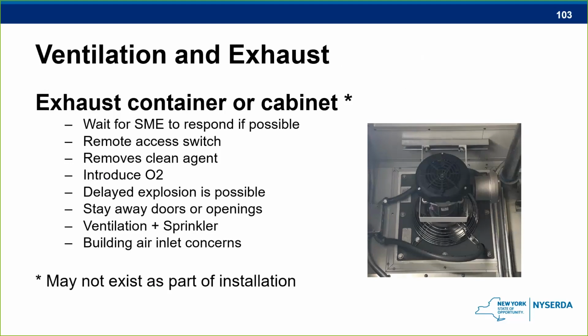But as I also mentioned, during an abnormal situation in lithium-ion, if we get that flammable cocktail and now it's stuck inside the enclosure itself, how are you getting that stuff out of there? And this is what some people are adding into their enclosures. If that stuff comes out automatically, where it doesn't get trapped inside the enclosure, then they should be good to go. Does that mean there's no explosion? Well, I can't say that. Some of that stuff can still get caught in some of the pockets of the enclosure. It's not practical to put one of these fans in there. Eventually it will come out.